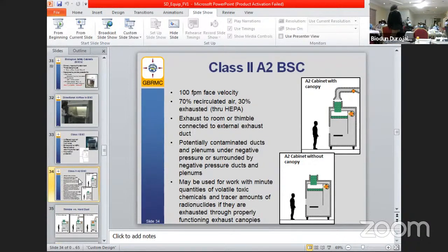How would you know that the lifespan of that filter is fine without certification? That is the work of the biomedical engineer. That is why the biomedical engineer is there to certify it and tell you when next I'm coming to recertify. So it's a cycle. Even without investing, I'm not working like that, so it's a bit strange to listen to this one. But I just assume, for common sense, that when the filter is paid, it should be an indicator.